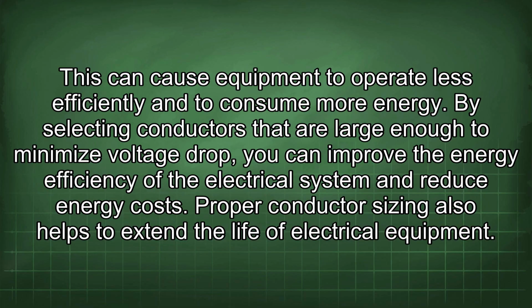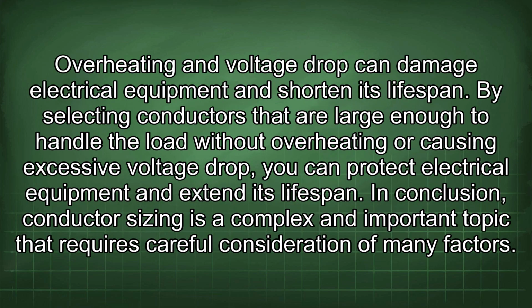Proper conductor sizing also helps to extend the life of electrical equipment. Overheating and voltage drop can damage electrical equipment and shorten its lifespan. By selecting conductors that are large enough to handle the load without overheating or causing excessive voltage drop, you can protect electrical equipment and extend its lifespan.